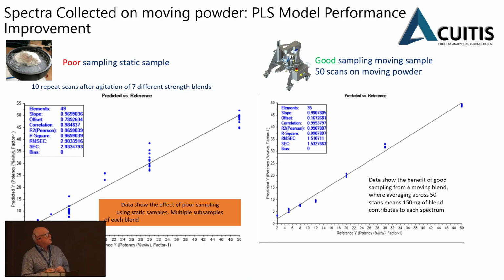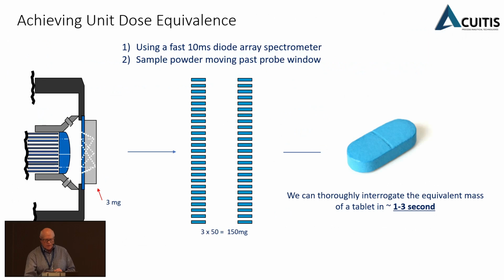Now on the right-hand side, we've actually put the powder into the simulator, and we're moving it and scanning it as it's moving. So essentially, what we're doing in that case is scanning our 3 milligrams, but we're moving the powder fast enough that every time it scans, new powder has been moved in front of the fiber optic probe. Now, in fact, this turns out to be useful. It was a problem, but with continuous processes, the materials are moving.